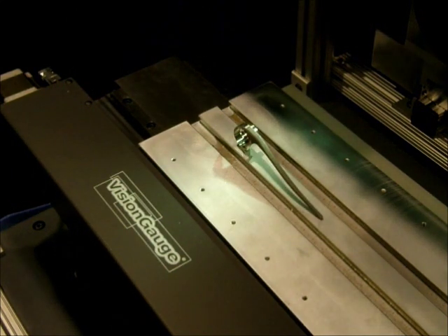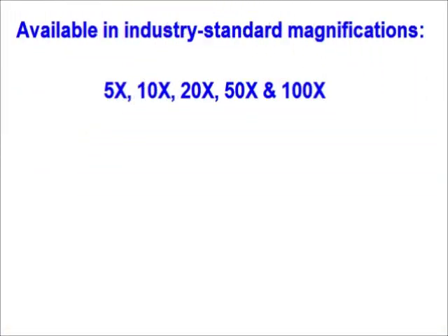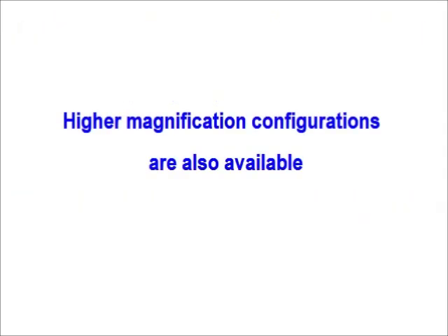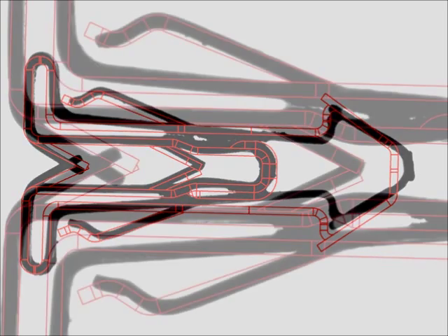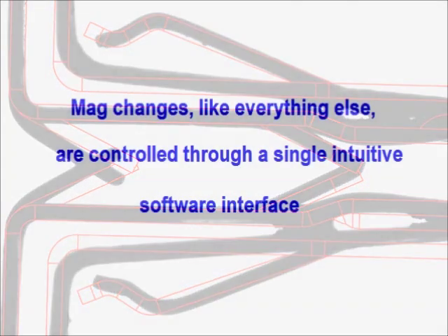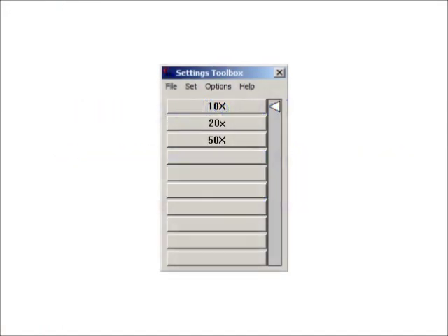The VisionGauge Digital Optical Comparator is available in industry standard 5x, 10x, 20x, 50x, and 100x magnifications, either in single mag or multi-mag configurations. Other higher magnification configurations are also available for specialized applications. Multi-mag configurations still have a single front objective lens, but under the hood there is a 3-lens encoded motorized rotary turret. Simply press a button in the software to change the optical magnification — the scaling of the CAD data and all of the optical calibration coefficients are automatically adjusted.